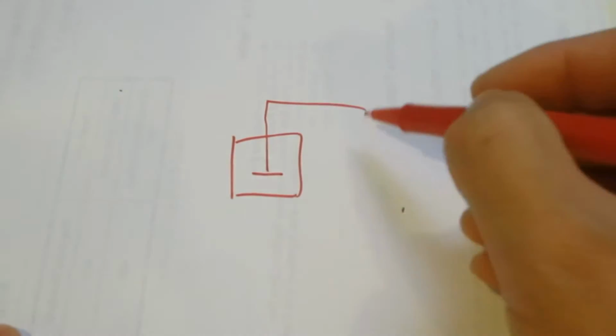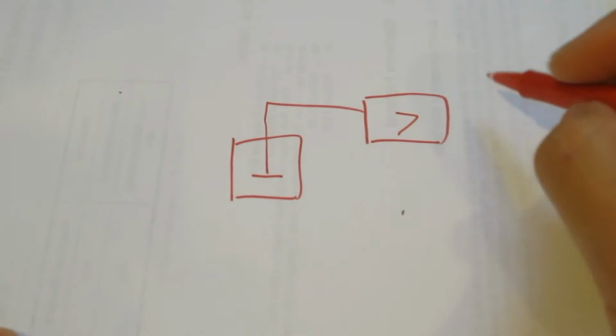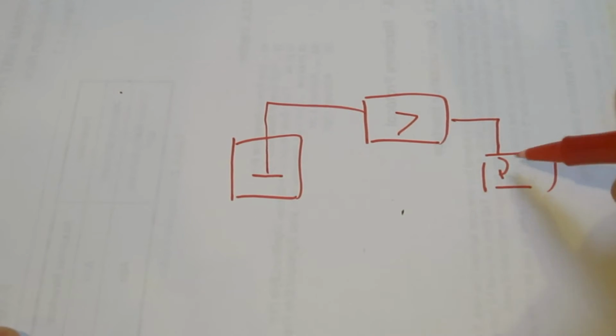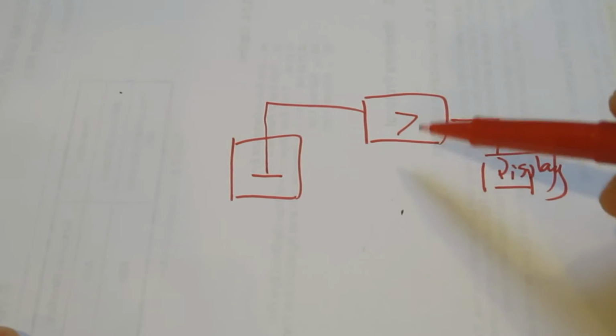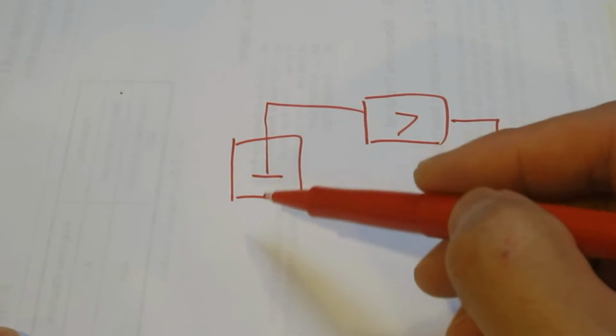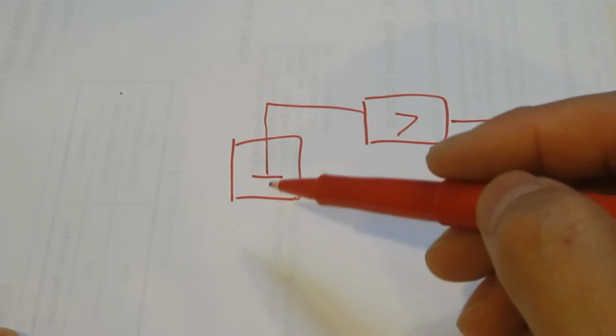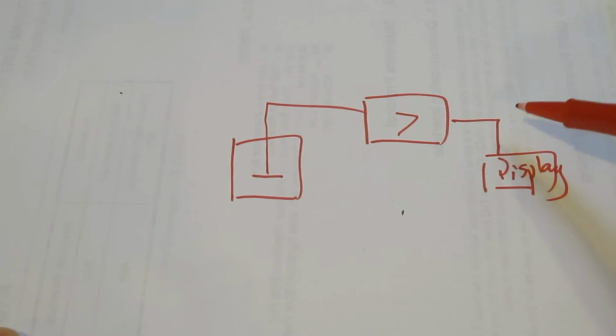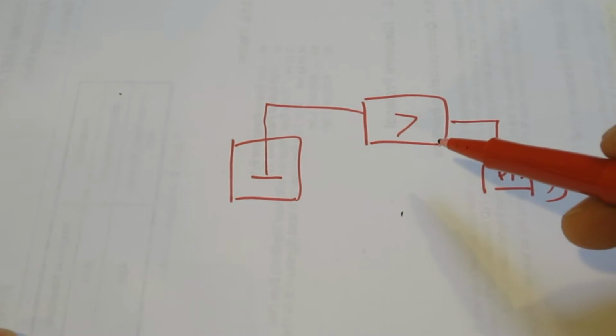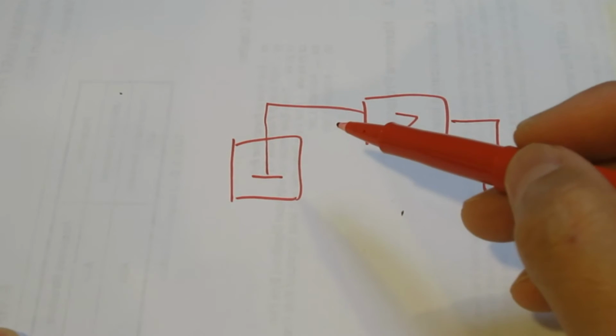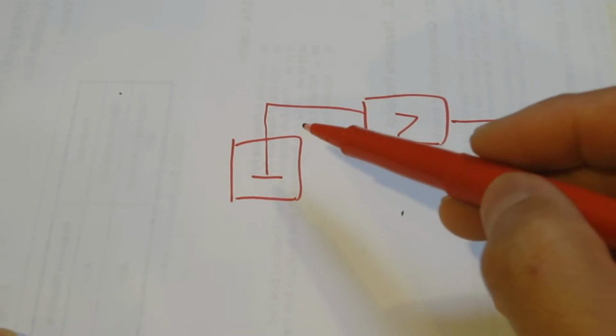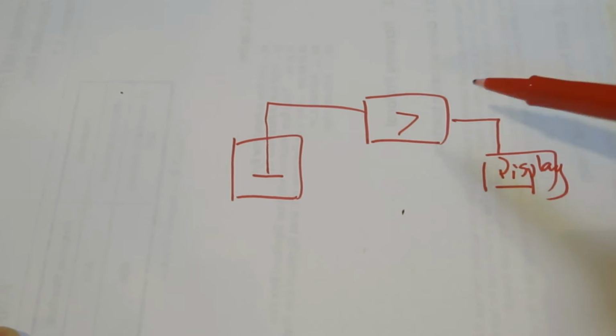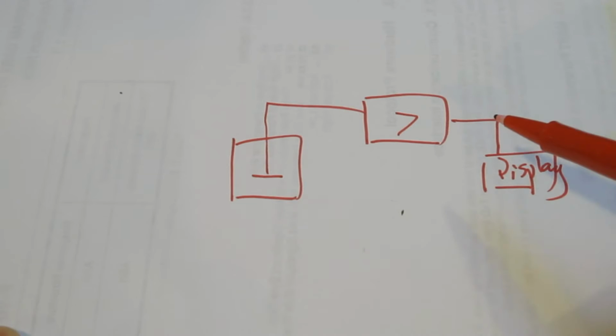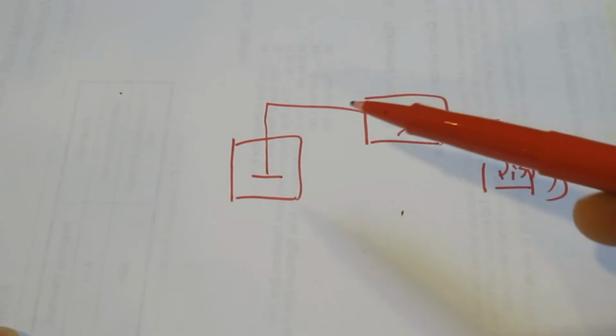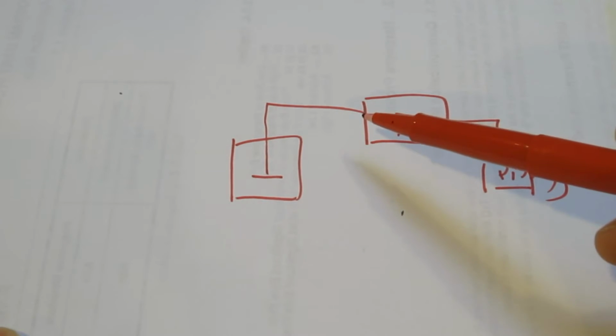So basically, we have a sensor here, and we have an amplifier, and then we have a display. Now, this is not just an ordinary amplifier, because the signal coming in is very, very small, and it's a DC signal. We want to make sure that we have very little offset so that we can obtain some meaningful readings back here. Typically, this is done via the use of a chopper stabilized operational amplifier. The principle of a chopper stabilized amplifier is to convert this minute DC signal into an AC signal, and then we amplify it as such. Any accumulative errors would be nulled out, because we're only interested in the AC signal rather than the DC component here.